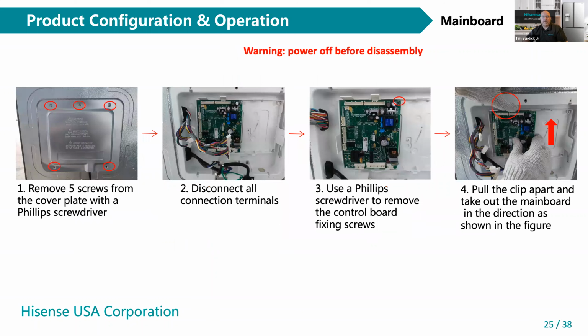My main user interface, my main control board, is on the back of the unit. There's a cover with 5 screws. Take those off and that gets me access to my main control, which is where I'll do most of my testing on this unit. To get the main control board out, I take out a Phillips head screw, and once all the wires are disconnected, I can just pull that board out.